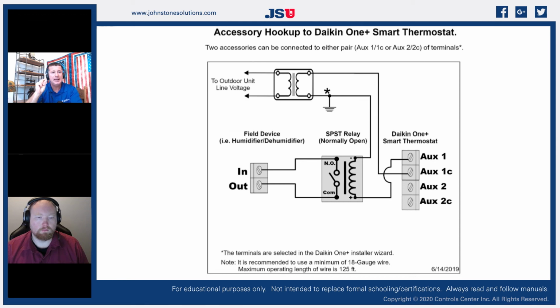So if I use an external component like a powered humidifier or a powered dehumidifier, and I run it through the contacts in my communicating system, I'm going to have an ungrounded signal trying to mix with my grounded equipment. And I will tell you that almost every time we have seen this in the field, it has broken the communication in our communicating network. So if you're adding a powered accessory to any communicating system, add an isolation relay, because that takes it out of the circuit. It takes that potential voltage out of there and allows our switch just to be a switch.